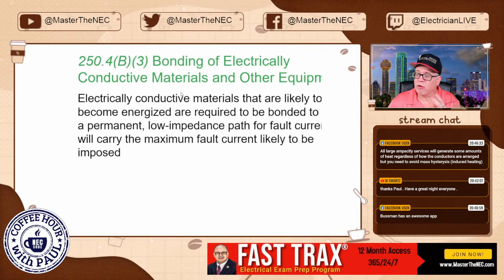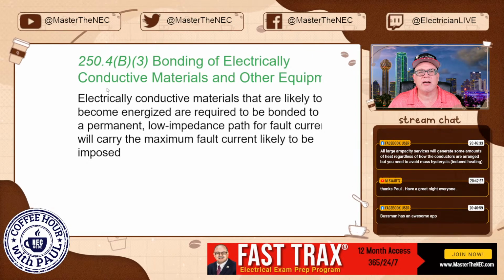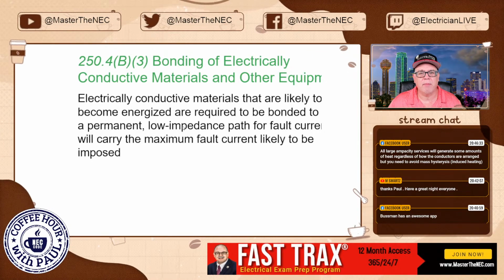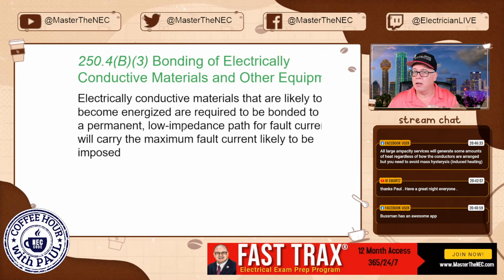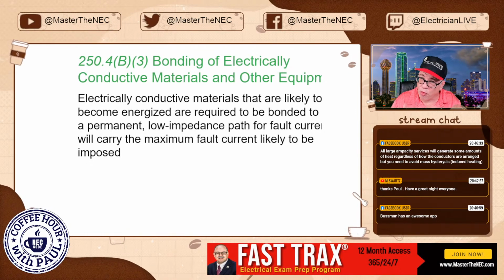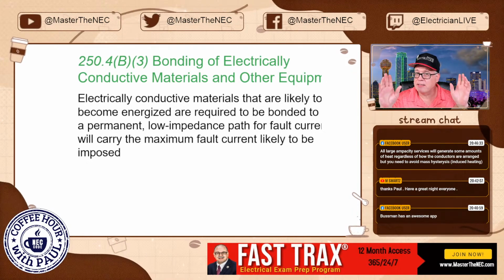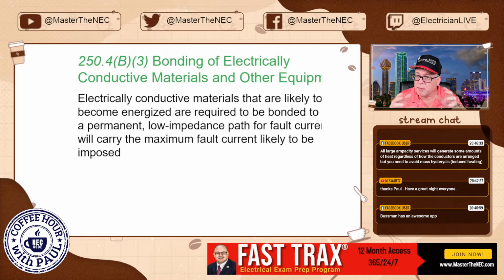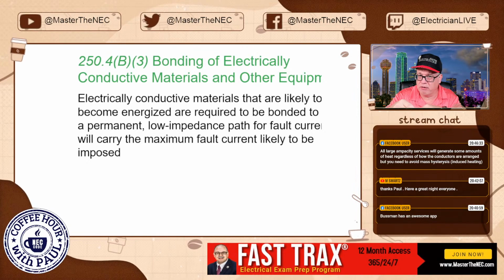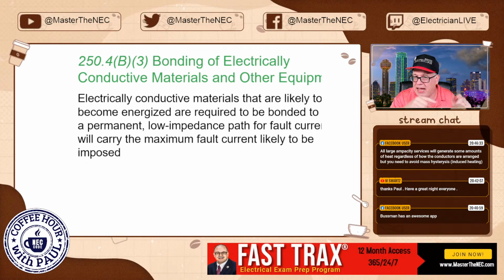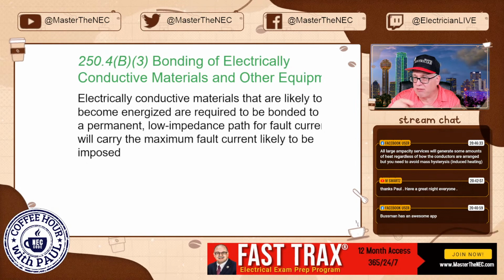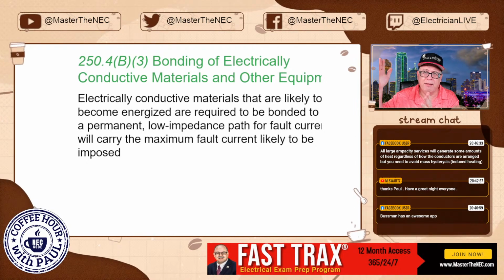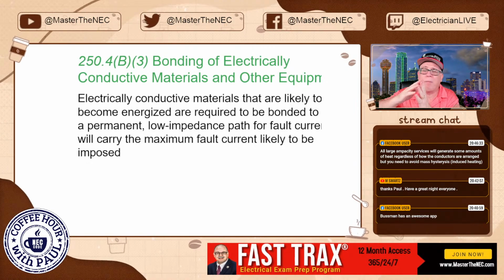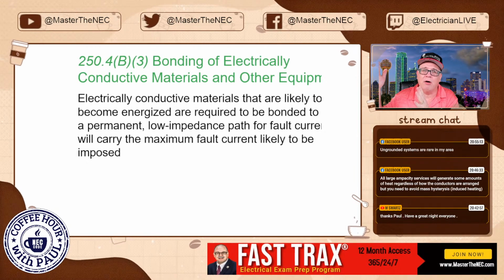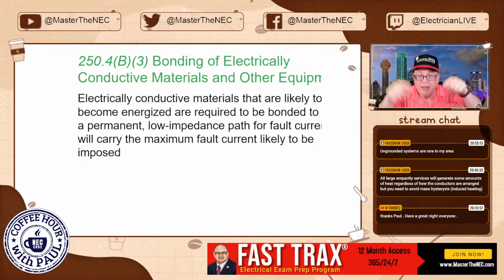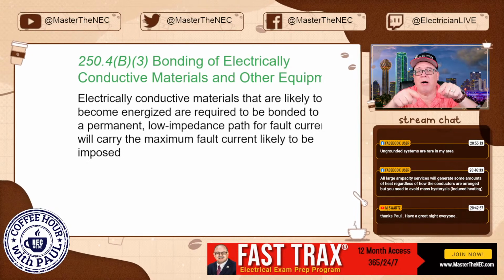250.4(B)(3), again, we're still doing ungrounded systems, says bonding of electrically conductive material and other enclosures. Remember, this is the performance. If you do everything right in the code, you're going to meet the performance of what we're trying to achieve right here. The same as we did for 250.4(A), same for (B). That's why 250 is so thick. There's so much to do. That's all prescriptive. But why are we doing it all? We're doing it all to meet these performance rules. That's why we're doing it all.